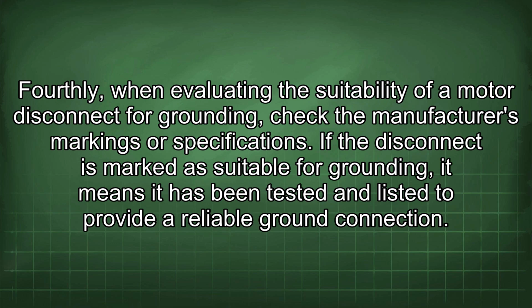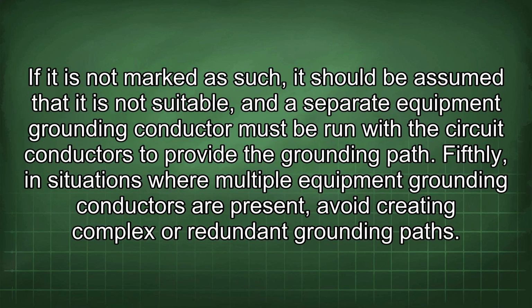If the disconnect is marked as suitable for grounding, it means it has been tested and listed to provide a reliable ground connection. If it is not marked as such, it should be assumed that it is not suitable, and a separate equipment grounding conductor must be run with the circuit conductors to provide the grounding path.